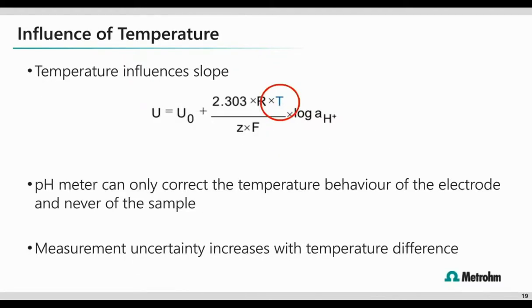You often hear when you talk about pH, temperature comes up. It's not important to have the entire Nernst equation memorized here. You might earn some bonus points though. But I think we can break it down more simply. Basically what you need to know is that temperature influences the pH value. If an electrode is calibrated at 25 C, then it should be capable of a linear measurement throughout the whole pH range and provide correct results.